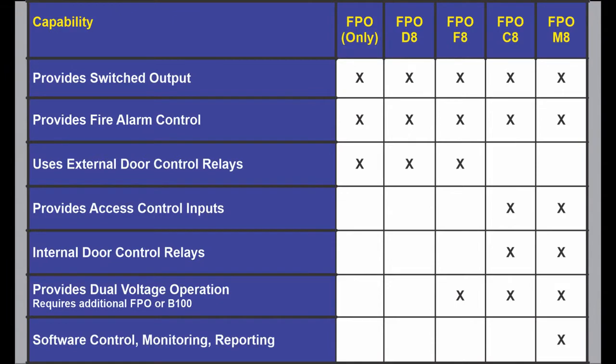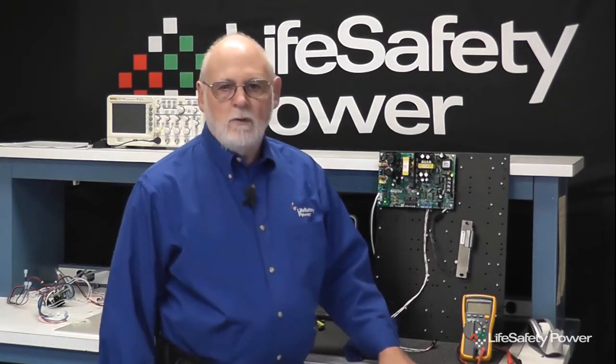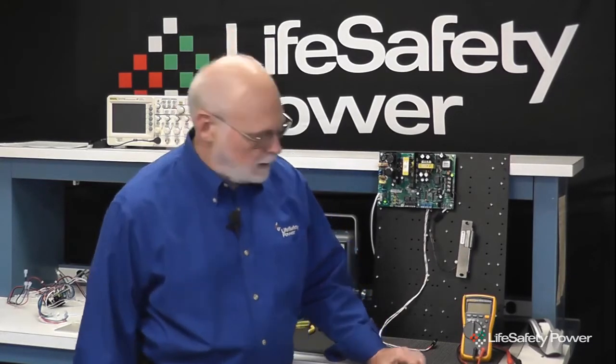We can use the FPO alone. When we use the FPO alone, we're using the fire alarm interface circuit built within the FPO. I can connect a switch contact directly to the FAI, and when I activate that switch contact, it will control the DC2 output in order to control the lock directly.